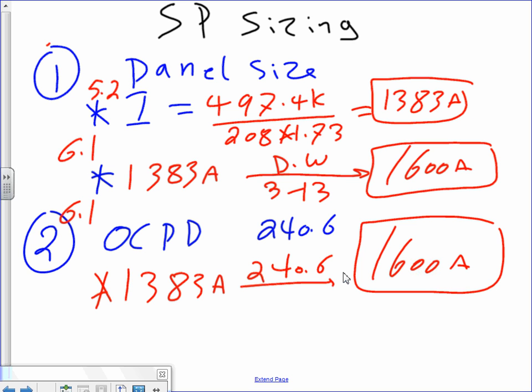This is where you find the actual panel sizes. That's all. Okay, so you take 1383 amps. Now remember, number one is a panel. We need a panel or a switchgear. Take it to DW, D wall, in this book. Page 3-13. This is the page you're looking at right here. When you go there, and I'll walk you through it in a second, it will tell you that they don't make 1,383 amp panels. You have to go to the next standard, which is 1,600 amps. Very easy. That's the panel. That's the box.